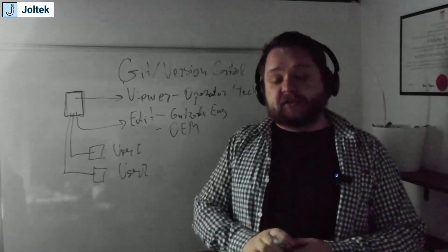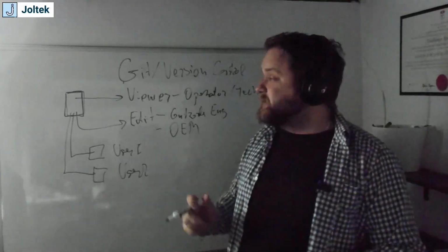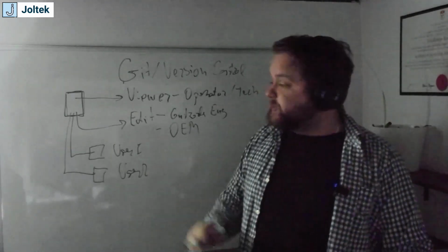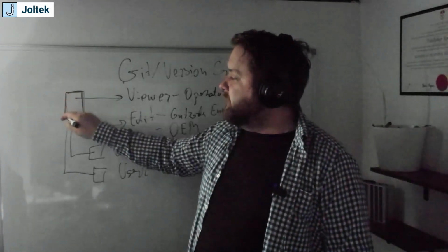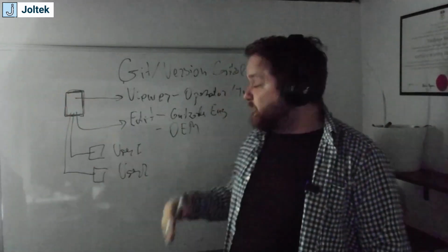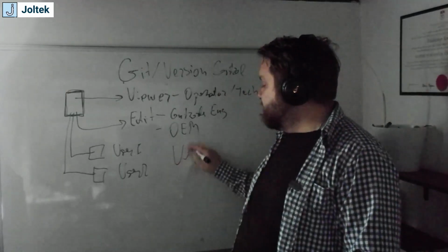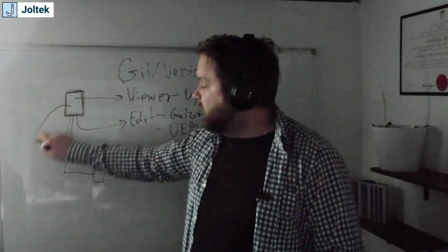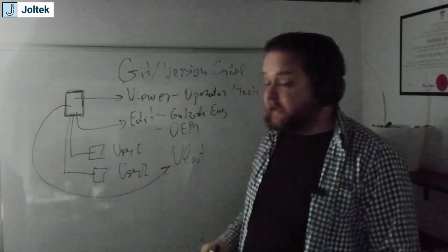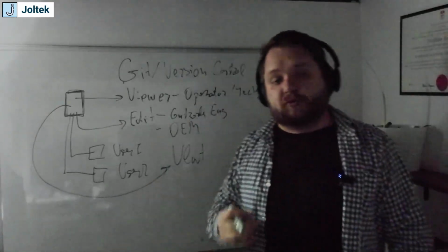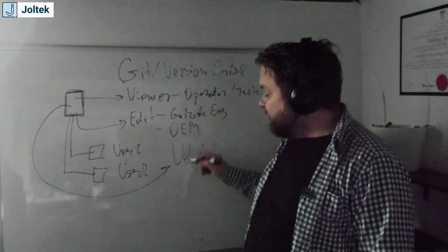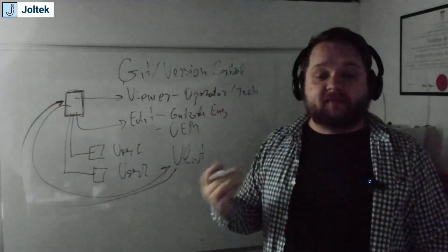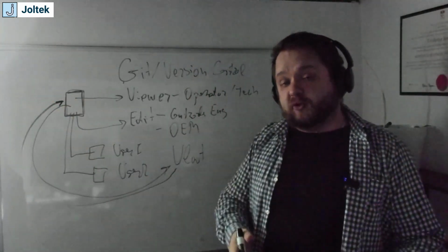The last feature that's extremely important in manufacturing, and you have this in Asset Center and other tools, is you can only have one copy allocated at a time. So for example, if Vlad is looking to make some changes, Vlad will basically check out the copy of this file, right? So this is going to go to Vlad, and nobody else is able to make those changes until Vlad pushes the file or the update back in, and then it can be validated before it's actually pushed to the PLC.